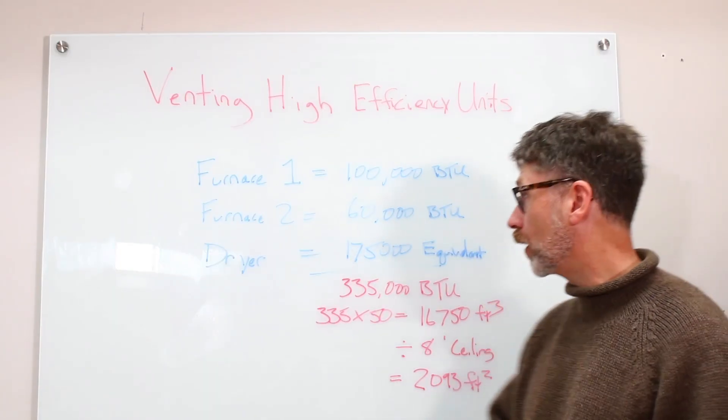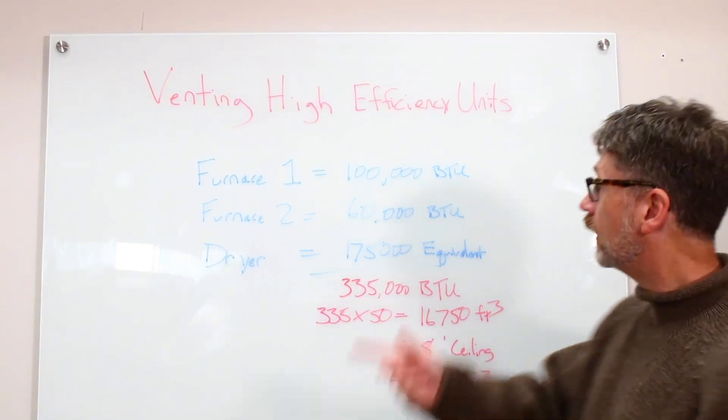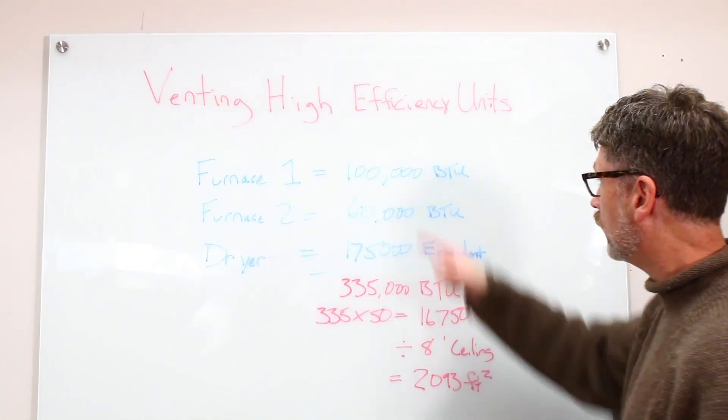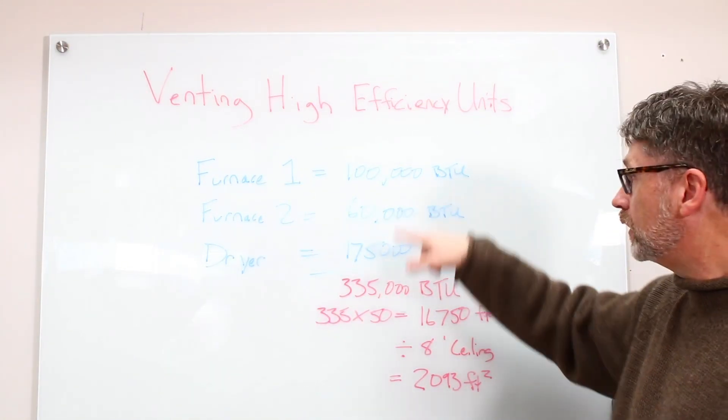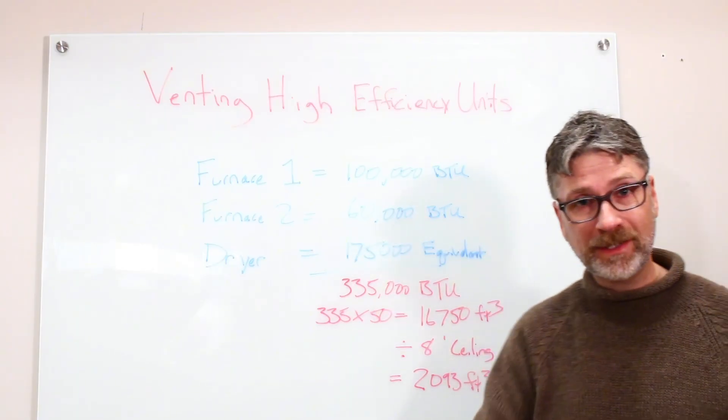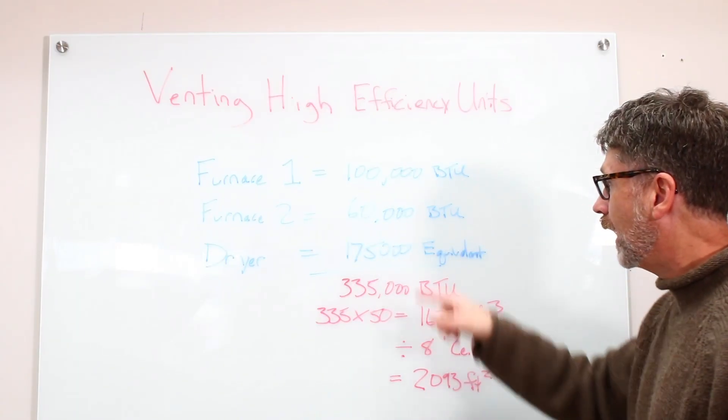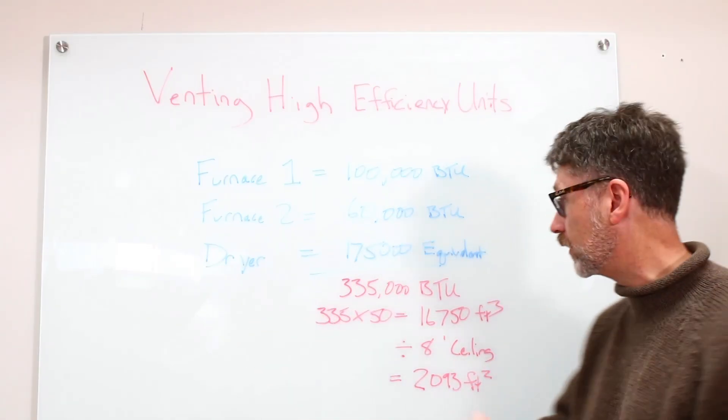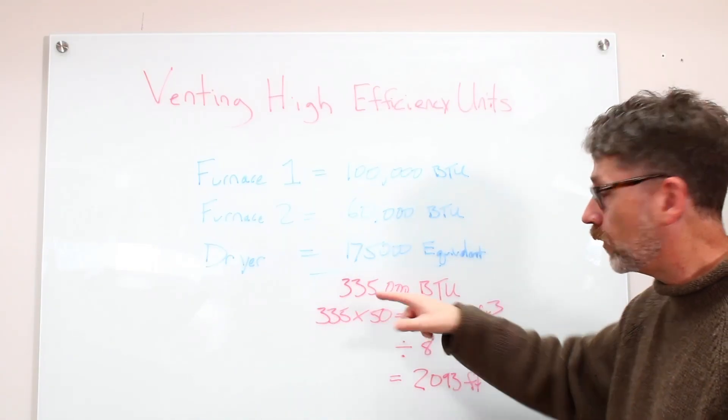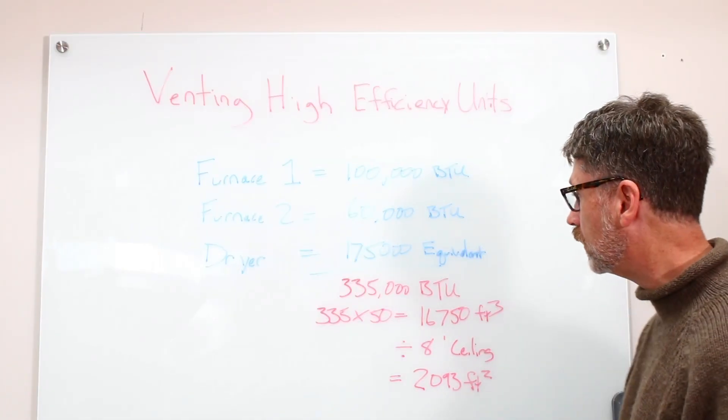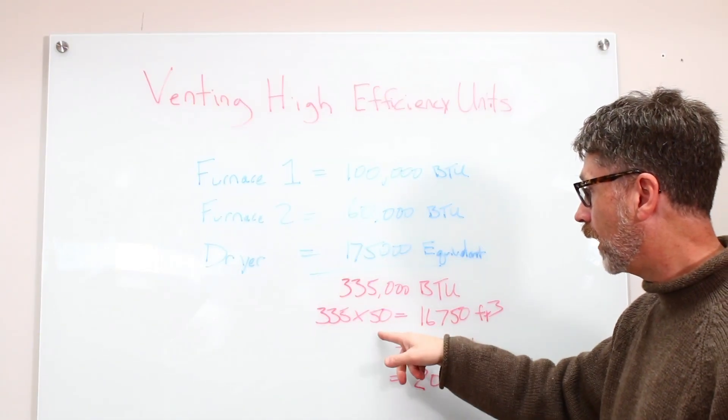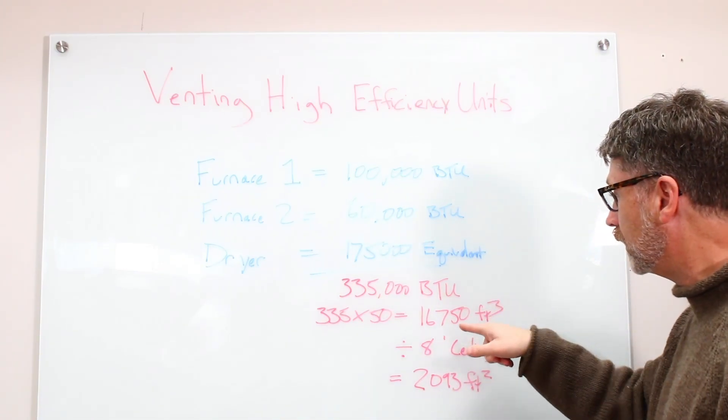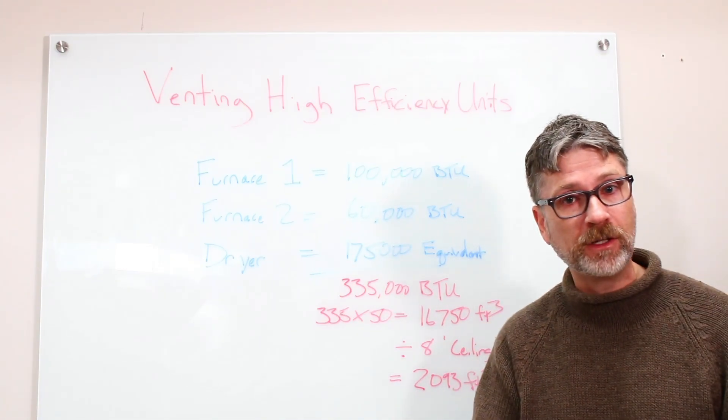Let's do a little math, and I'll show you how that works. I was recently at a home that had two furnaces and a clothes dryer in the basement. Furnace number one, 100,000 BTUs. Furnace number two, 60,000 BTUs. And we're using 175,000 BTUs as the equivalent for the dryer for how much air it exhausts. You add that together, we're at 335,000 BTUs.